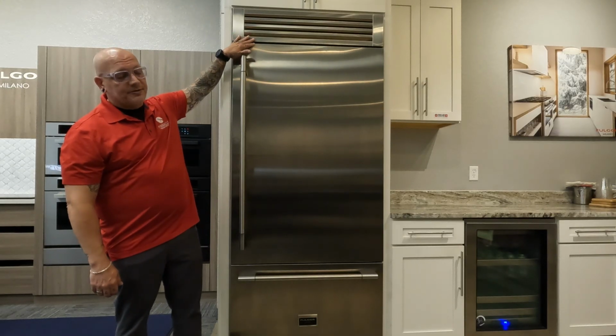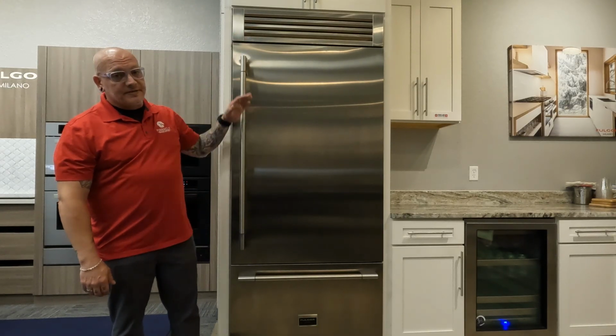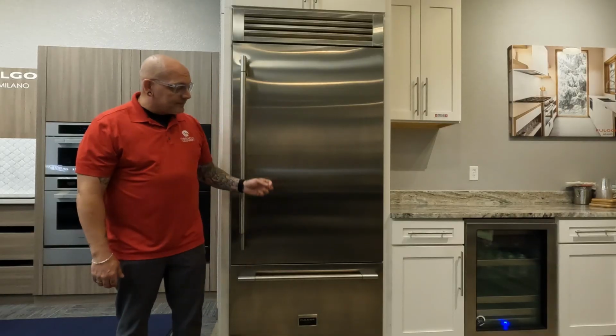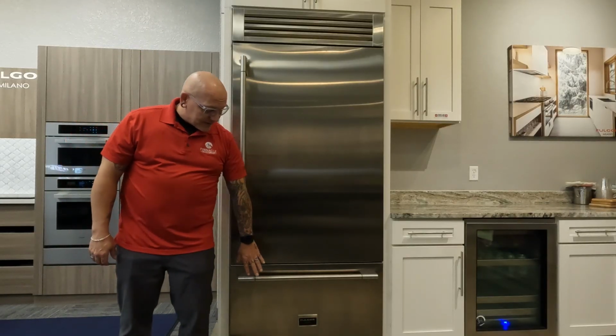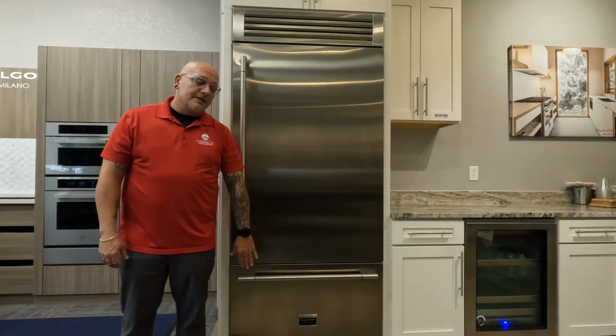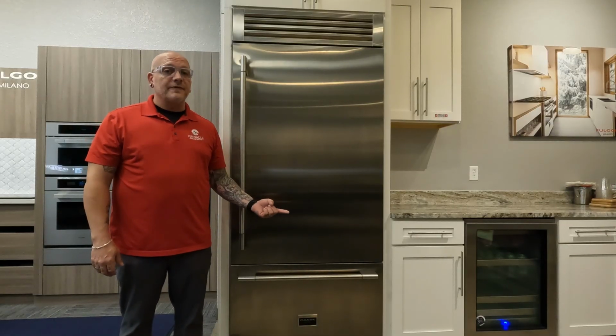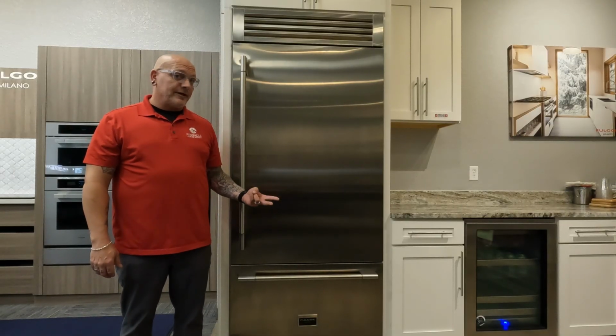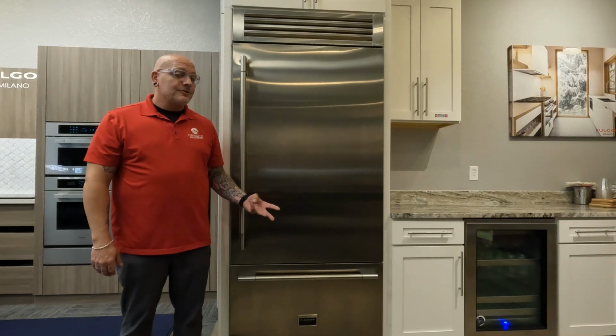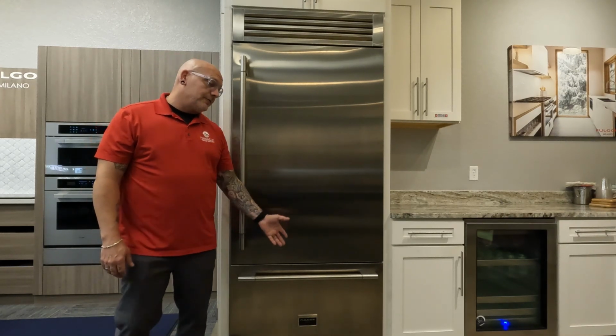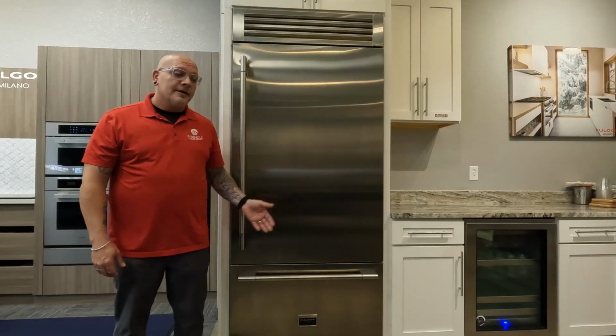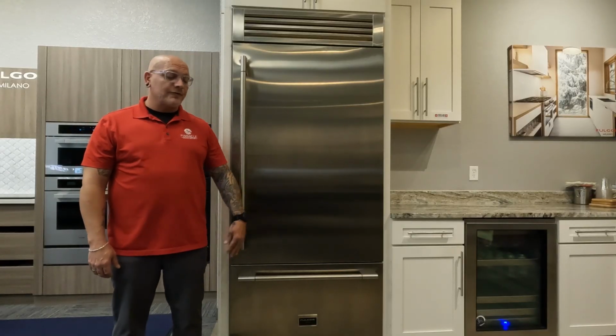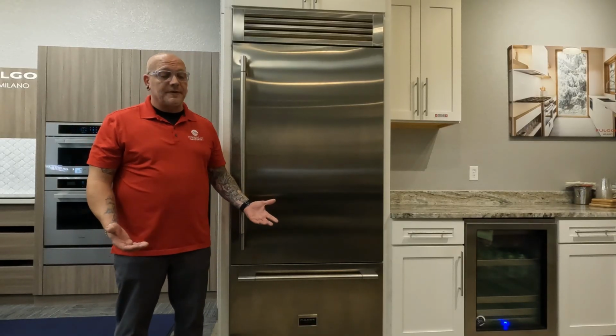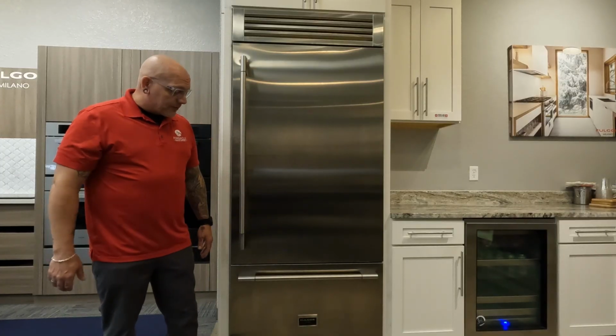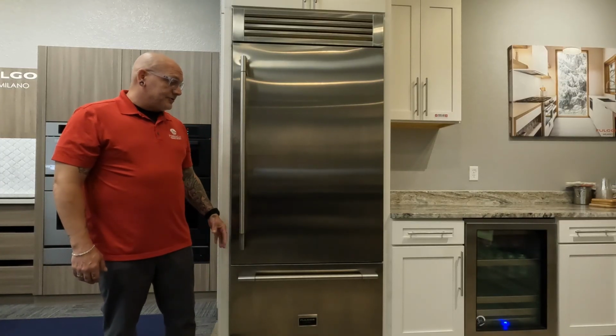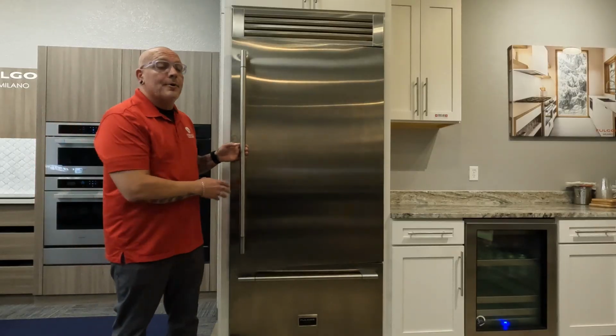This is a top mount compressor unit, not a column but an over-under, with a freezer on the bottom and fridge on top. They actually call this freezer a tri-mode section because you can change it from a freezer, which it comes as a default from the factory, to a fridge, to a Fresco cooler. So depending on how you want to work it, or if you want two machines side by side, you can change one into a freezer and one into a fridge, for juice boxes for your children or something like that. It's a beautiful product, cool that you can change it into three different modes. That's why it's called a tri-mode.